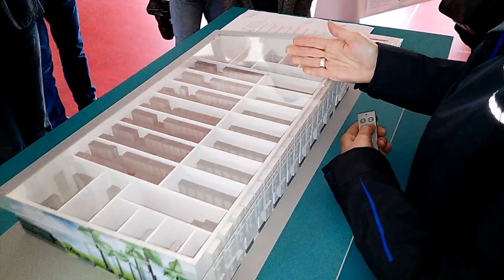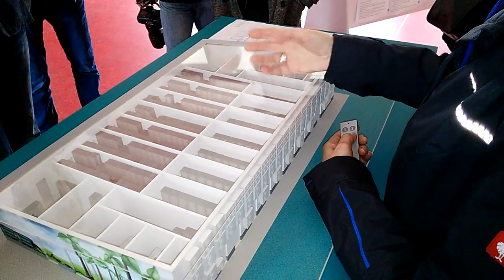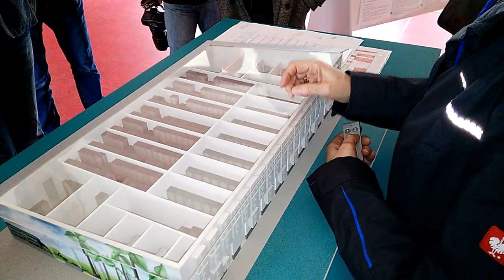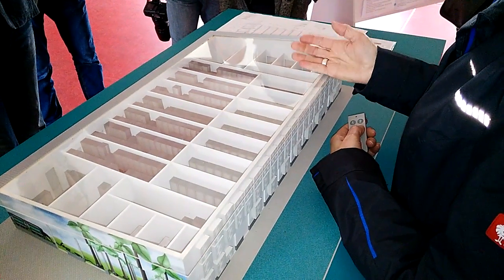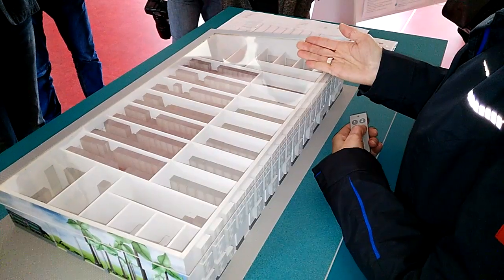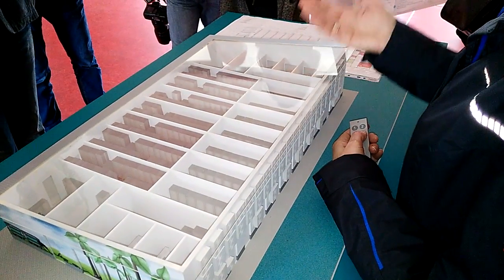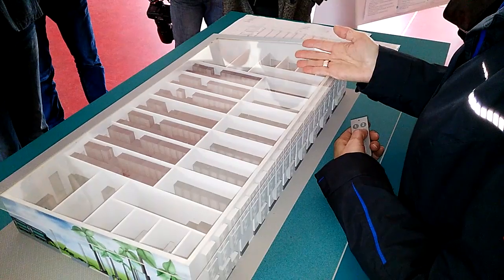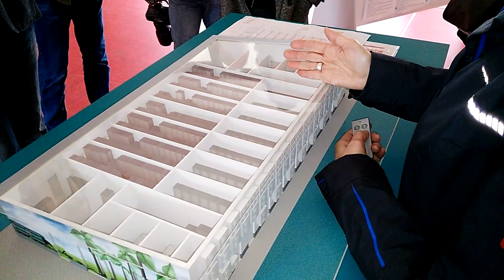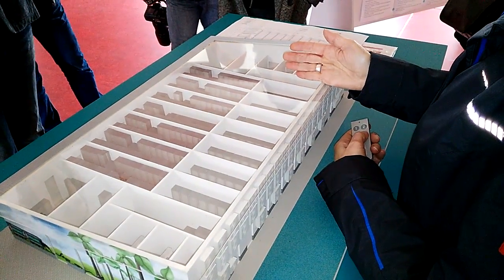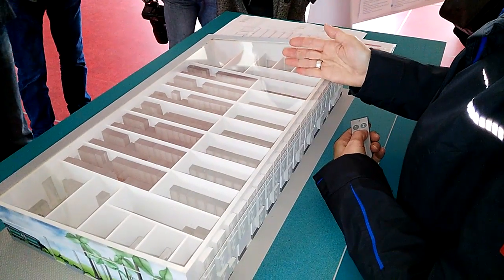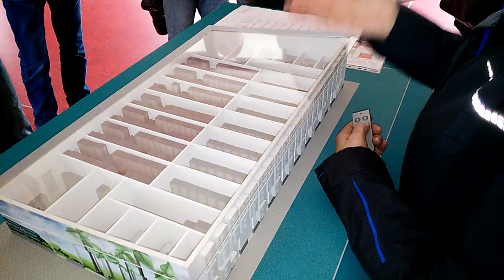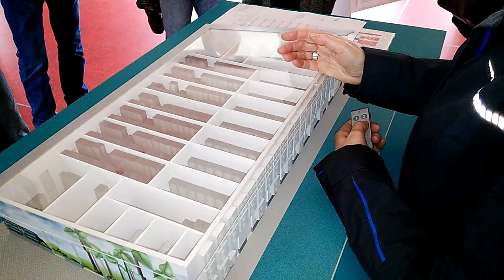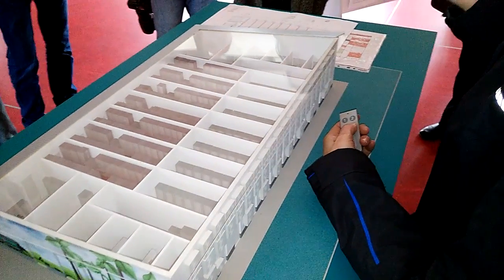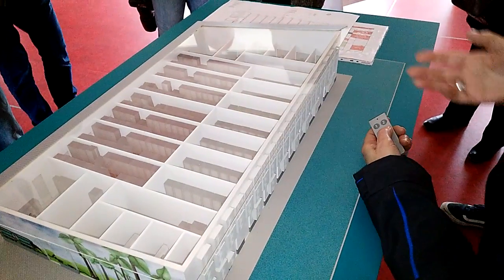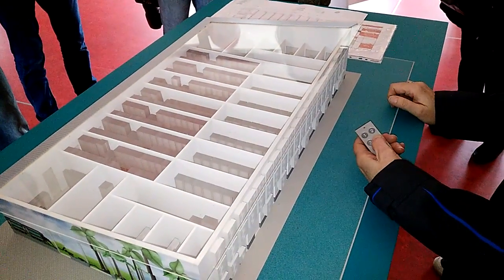What they've done is build in a few extra battery modules, so the first few that break down don't have to be replaced straight away. It's officially a 10 megawatt system, and they're paid on that basis, but it's actually a 10.7 megawatt system, so it has more capacity than it needs. That way, as soon as one starts to play up, they don't have to rush out and replace it immediately, they have a bit of flexibility.